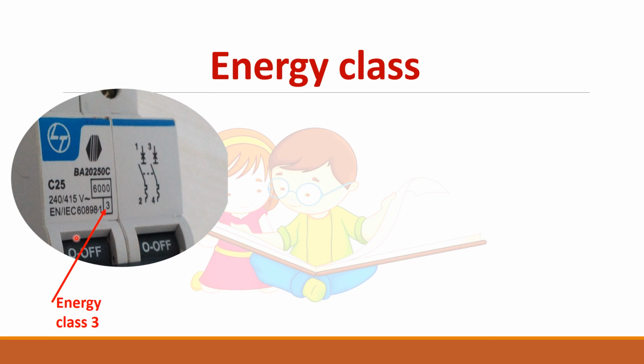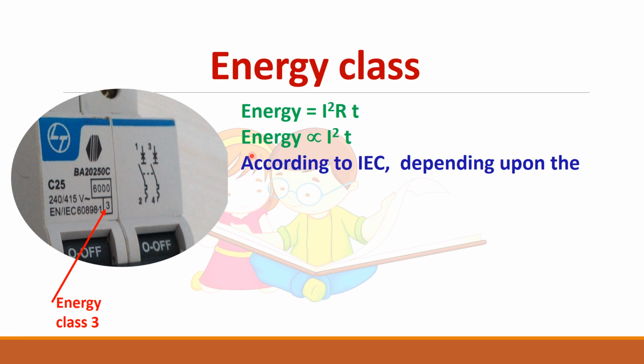Next we will see about the energy class. This is represented by the number 3 here. We know energy is power into time, which is given by I square R into time. If R is constant, we can write energy is directly proportional to I square into T. So what does this mean? Whenever a fault occurs, the tripper takes some time to completely trip. So this current into that time will contribute to the energy. The breaker should respond as fast as it can, or else it will let through more energy and damage the breaker. So this energy should be very low.